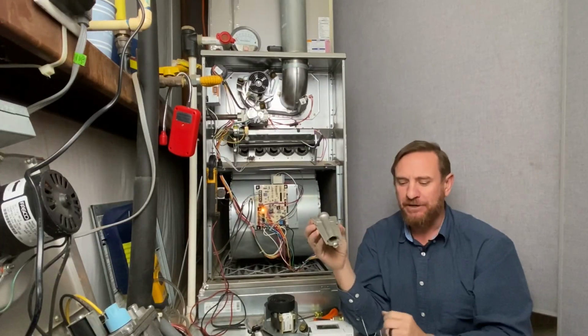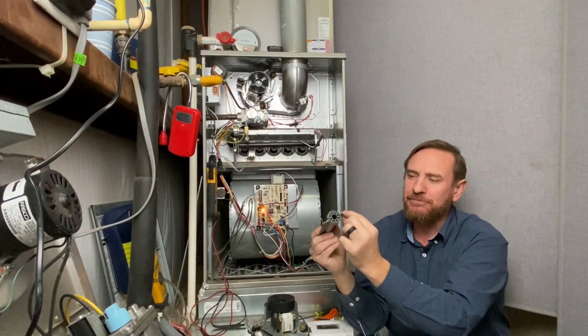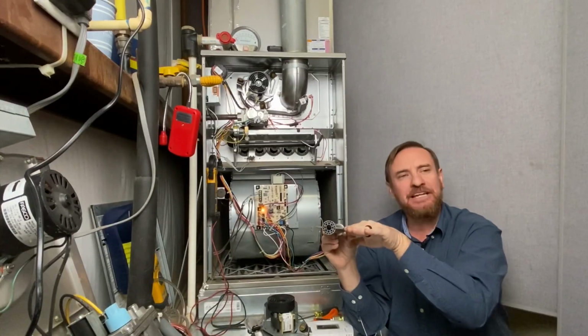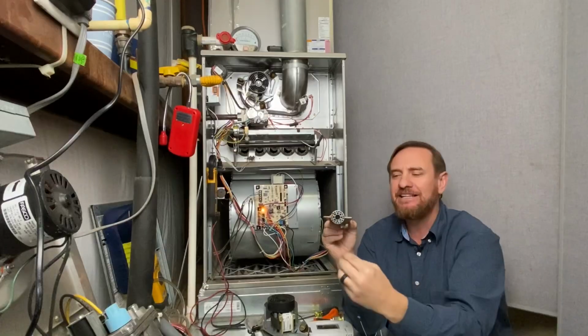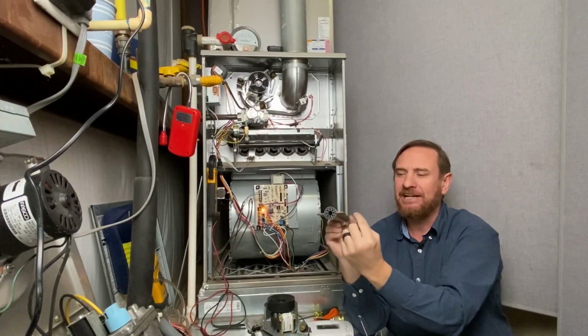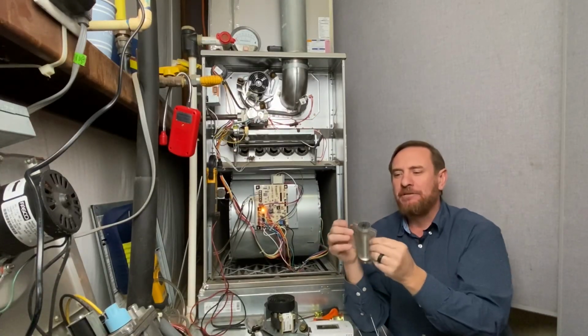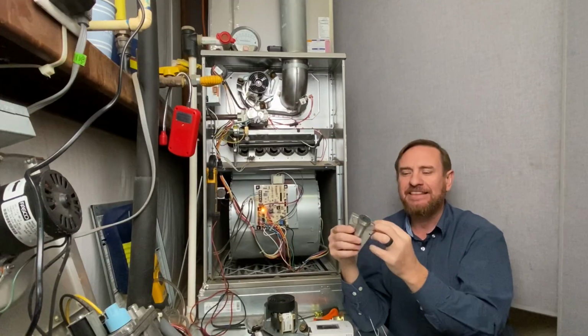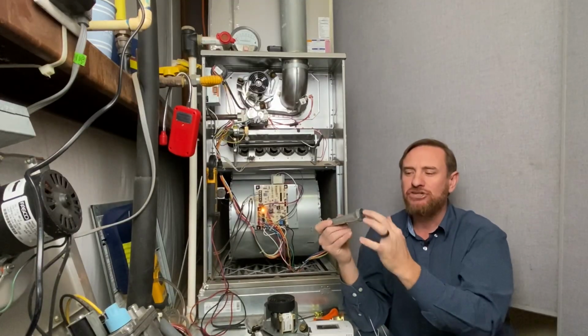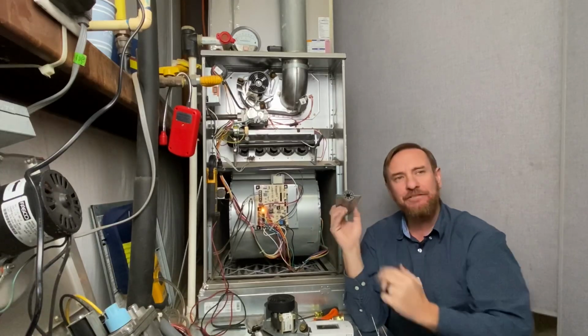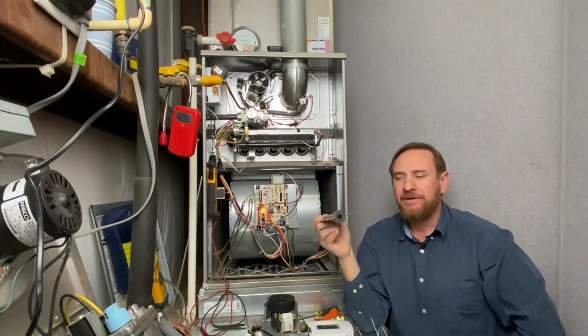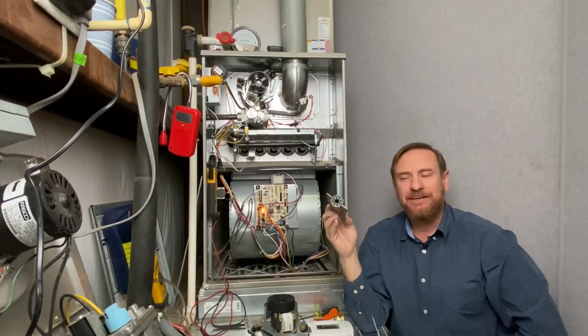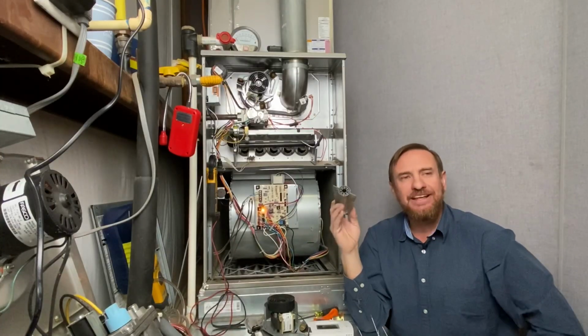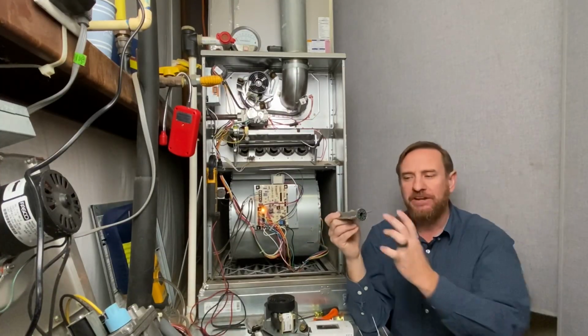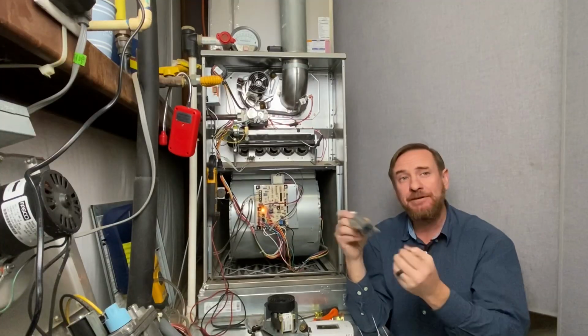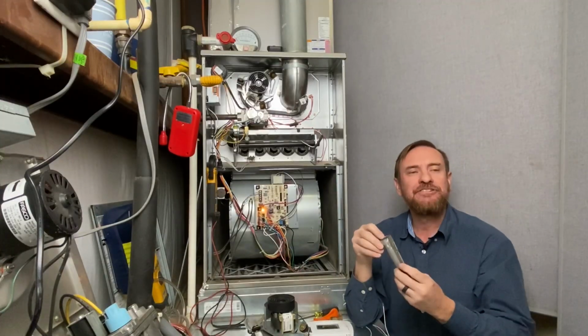So this is an in-shot burner, and it's important to see that there's little bitty lines on both sides of these. There's another one that lines up beside this one. So the main flame's coming out into the heat exchanger, but there's also this side tube right here that lights the next burner. It's important to make sure that these don't have rust or anything like that. They can start to rust up. That can be an issue. You can pull them out and clean them, but you need to be thinking, if there's rust on this, where's the moisture coming from? Is it leaking water? There's some other issue you need to get fixed. I've seen these units that were 20 years old that never had a bit of rust on them. So if they're rusting up, you need to be thinking, where is that coming from, and what else is that rust causing?